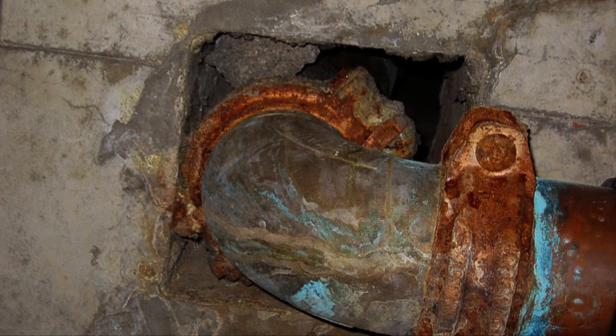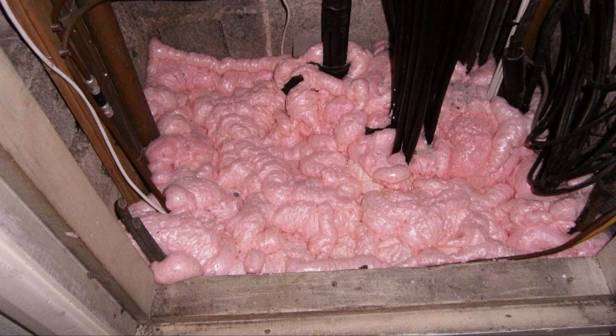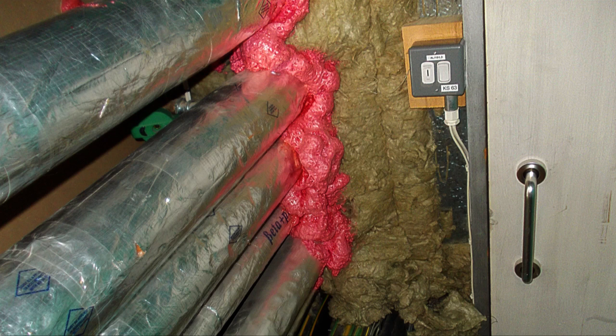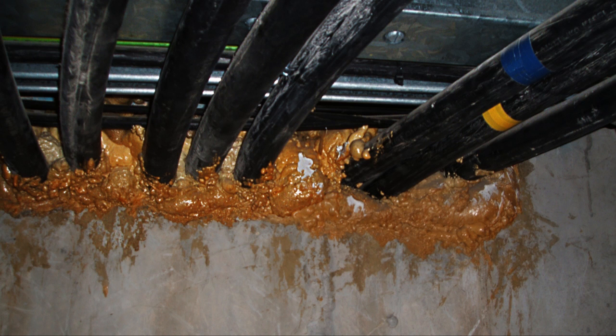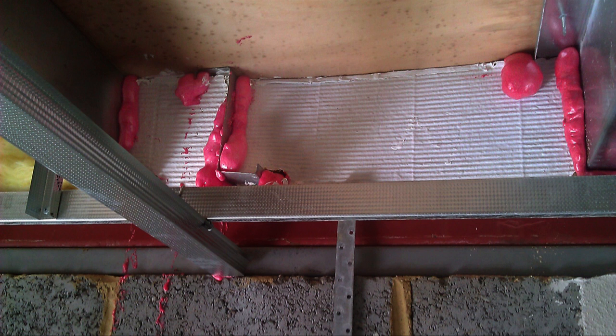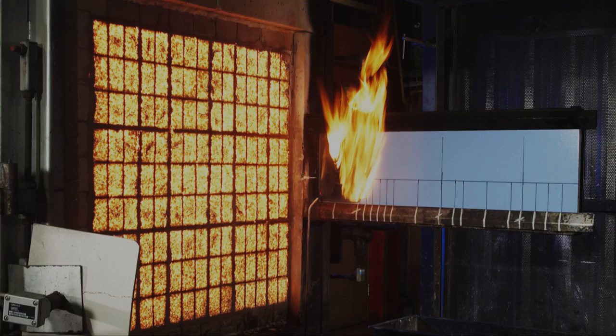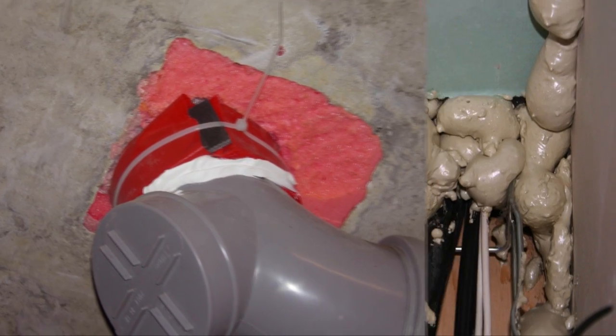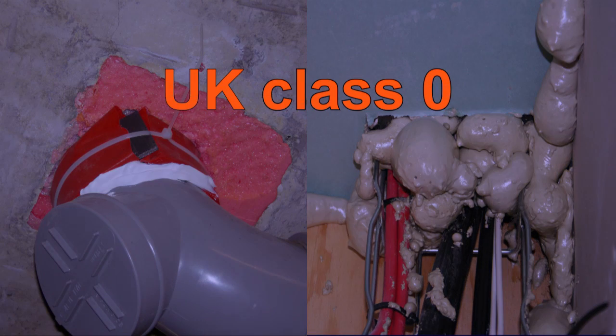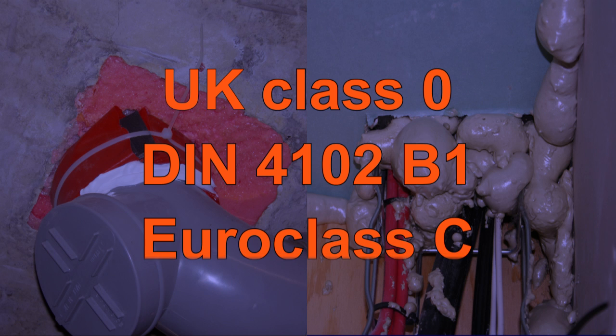One such example, which is increasingly being observed, relates to the inappropriate use of so-called fire-rated polyurethane (PU) foams. There are two issues. Firstly, they are sometimes sold on the basis of their performance in less severe reaction to fire tests. Such foams may be coloured to indicate a performance, such as UK Class 0, German DIN 4102 B1, or Euro Class C.